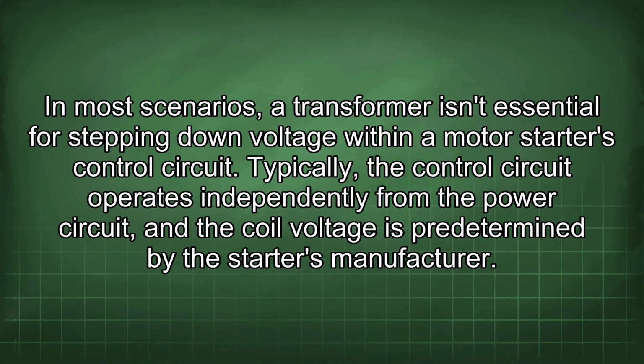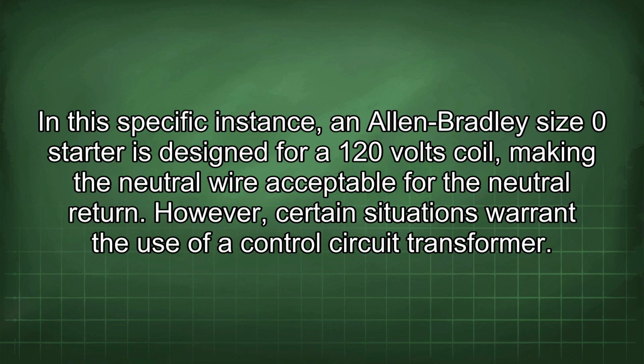In most scenarios, a transformer isn't essential for stepping down voltage within a motor starter's control circuit. Typically, the control circuit operates independently from the power circuit, and the coil voltage is predetermined by the starter's manufacturer. In this specific instance, an Allen-Bradley size 0 starter is designed for a 120 volts coil, making the neutral wire acceptable for the neutral return.